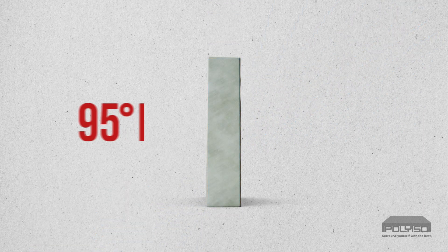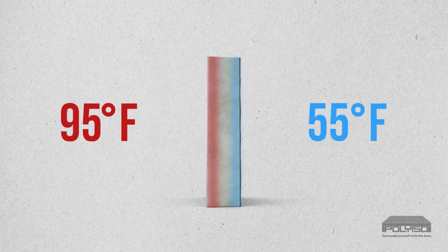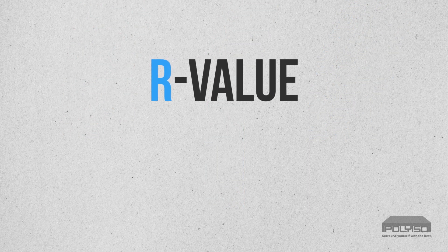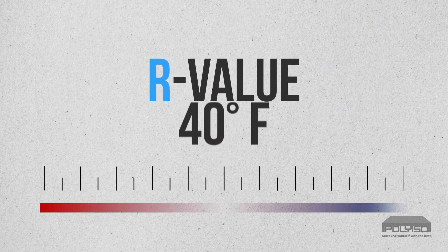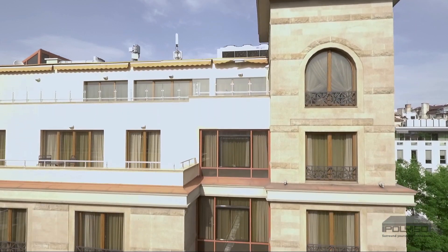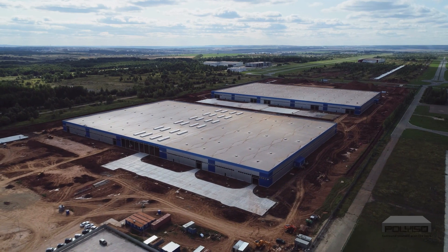This mean temperature establishes a consistent baseline for measuring R-value when testing or comparing products. For example, working in degrees Fahrenheit, if the hot surface is 95 and the cold surface is 55, the mean temperature is 75. If we target 40 as the mean temperature, the hot and cold surfaces could be set at 60 and 20. R-value is typically measured with at least a 40 degree Fahrenheit difference between the hot and cold surfaces to ensure sufficient heat flow through the sample.